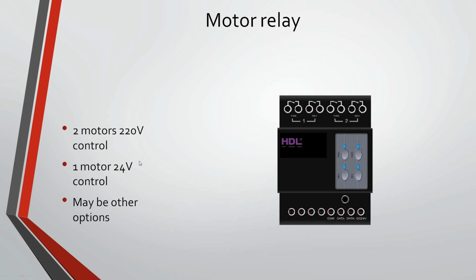If you use 24 volts control, you usually can control just 1 motor with this device because you need 3 channels. You need to get plus and minus to get up, minus and plus to get down, and disconnect them to stop. So for this stop channel, you need to use the 3rd one. And you need to use 2 24 volts power supplies usually.